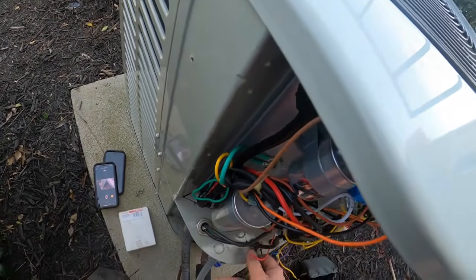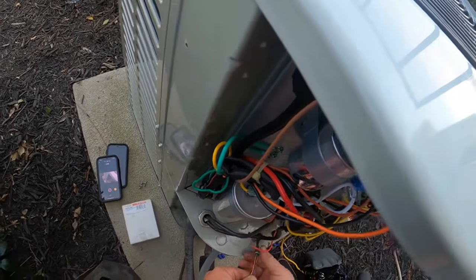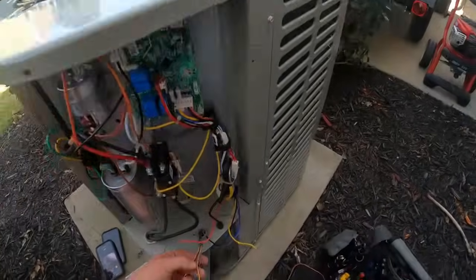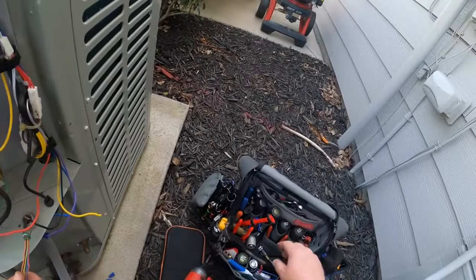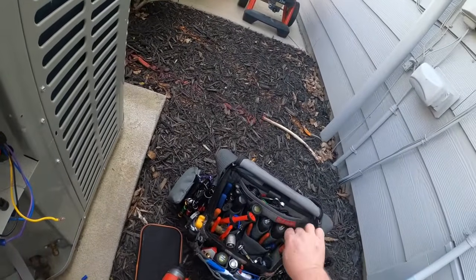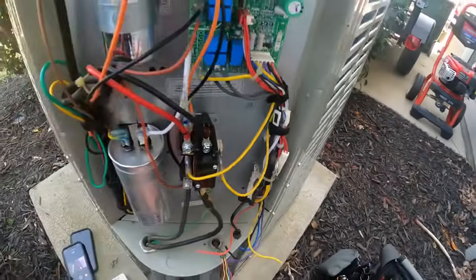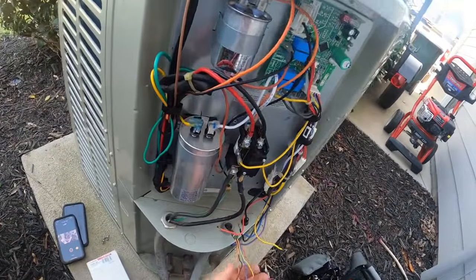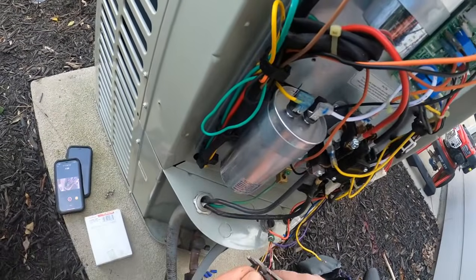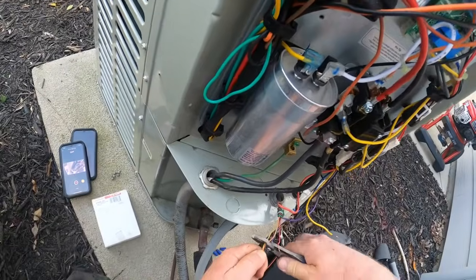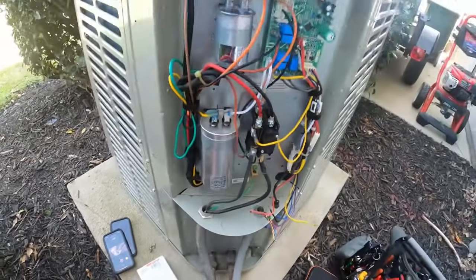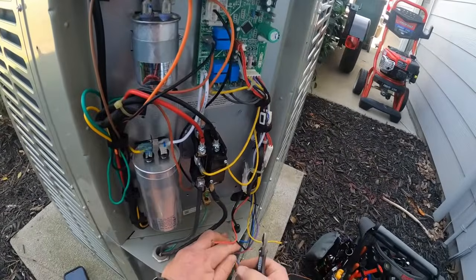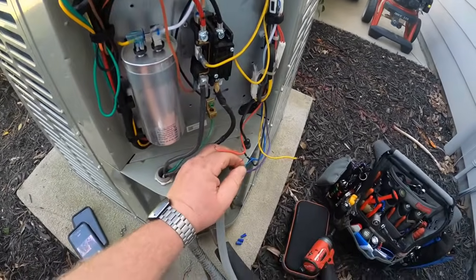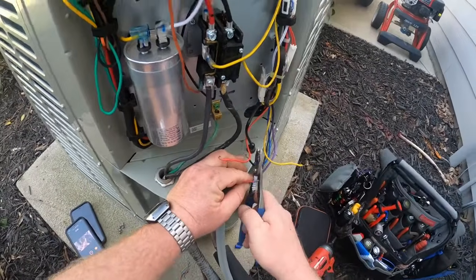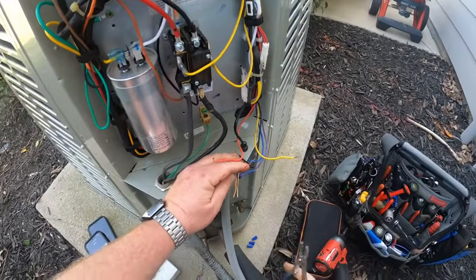But I think I'm going to set that up in that furnace or that zone board a little differently. I just want to be sure that when this thing goes through defrost cycle, we're not kicking on the furnace. You don't want to have the furnace running at the same time as the heat pump, things like that. So you just want to be careful. But with everything set up properly, that should work. I've done this before. It'll be fine.